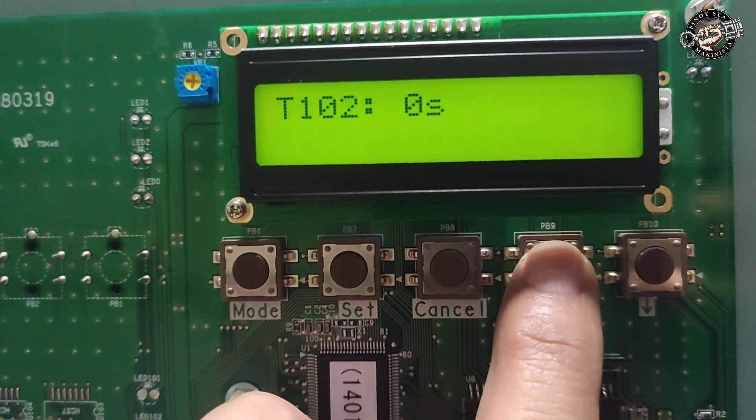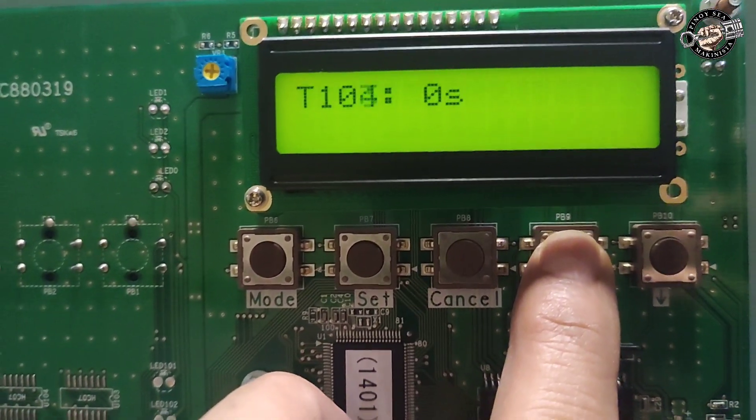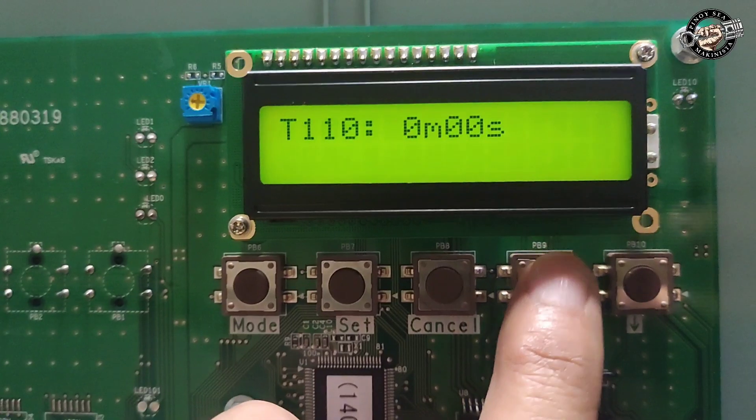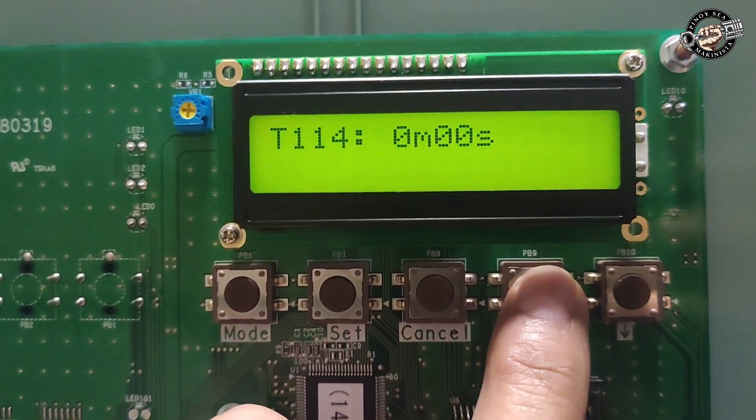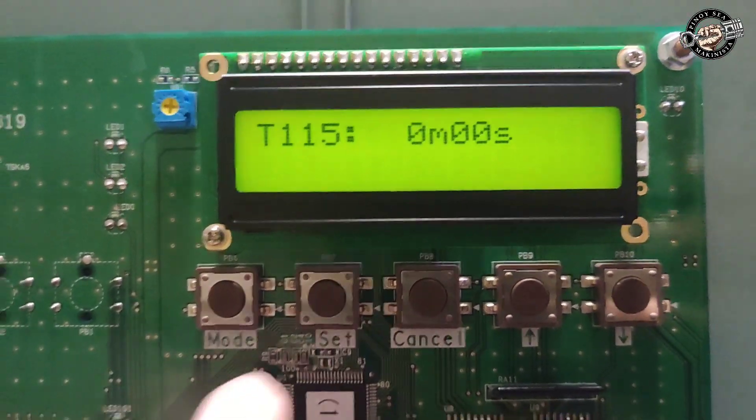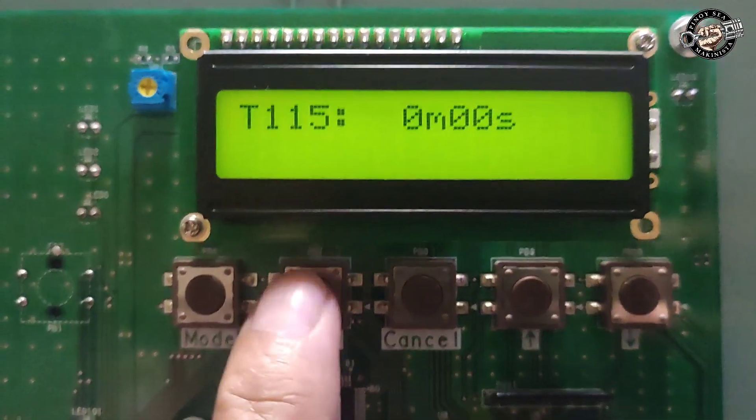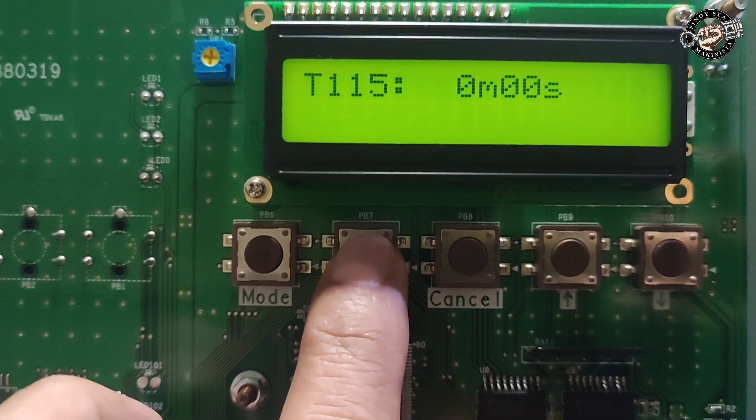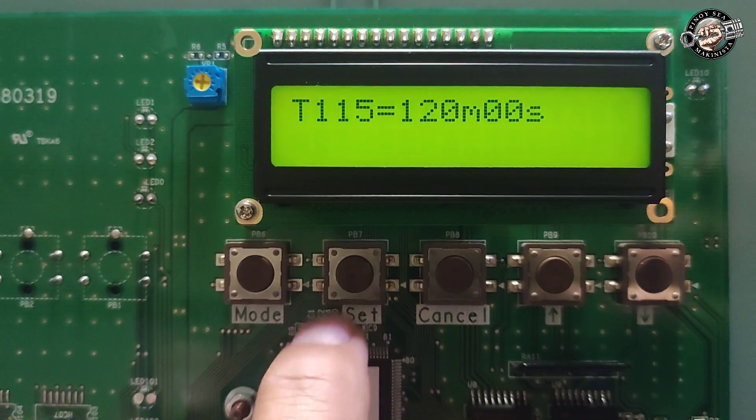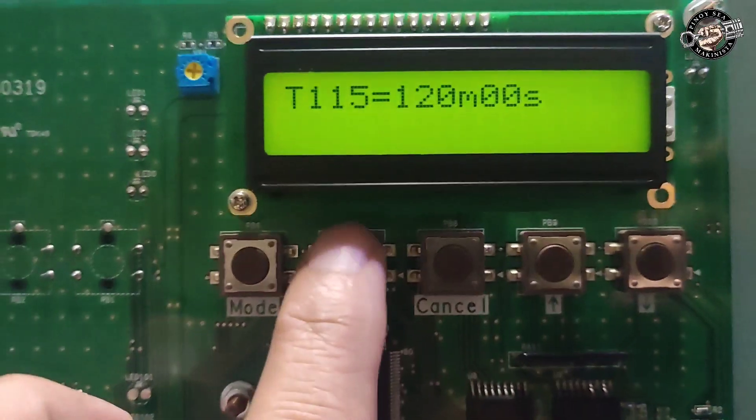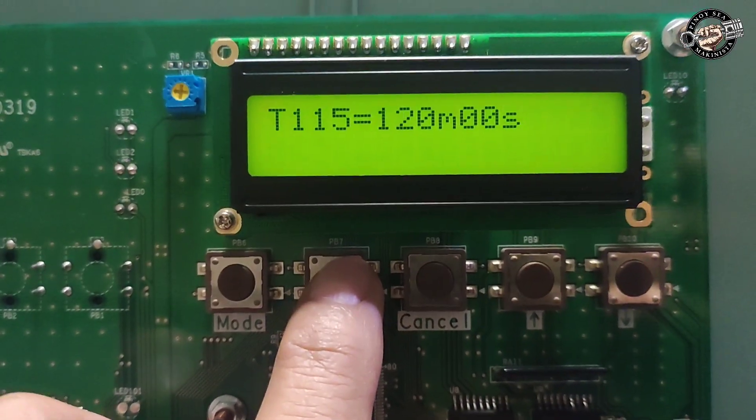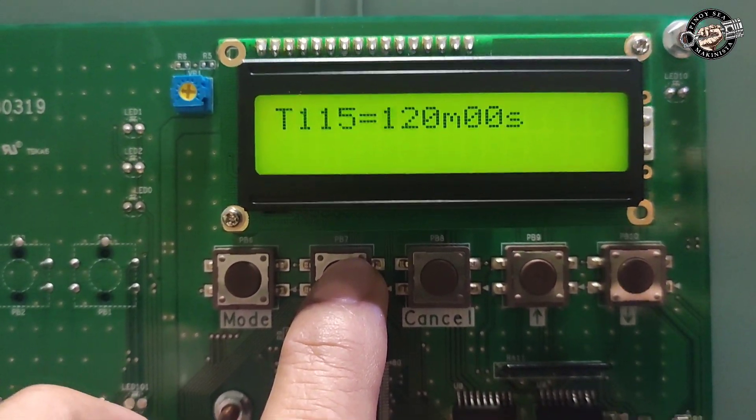For sludge discharge intervals, select T115. Press the set button and you can see the set value like 120 minutes 00 seconds. The setting is 120 minutes 0 seconds set value to adjust.